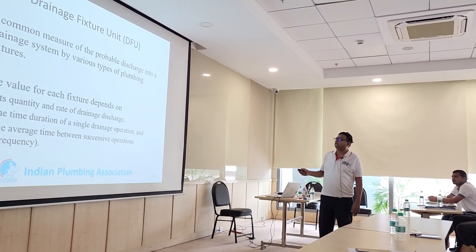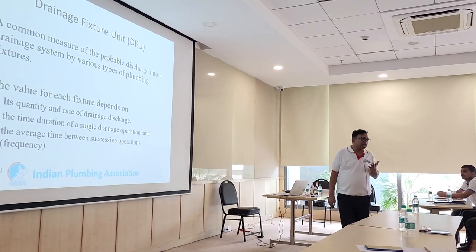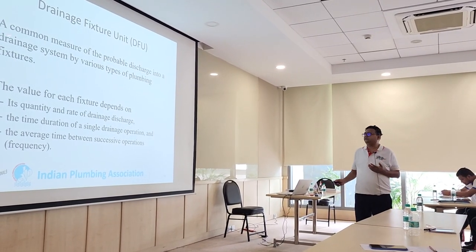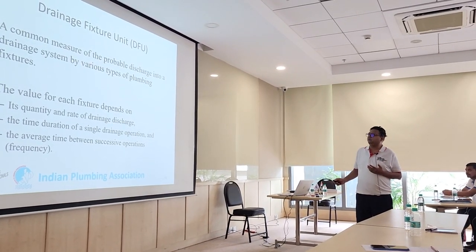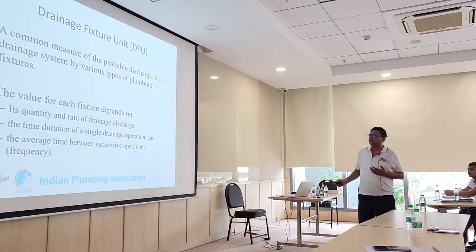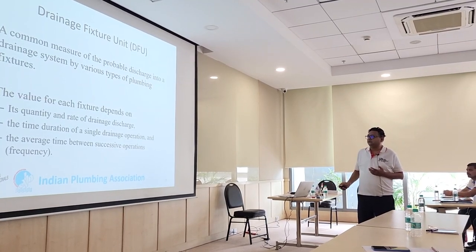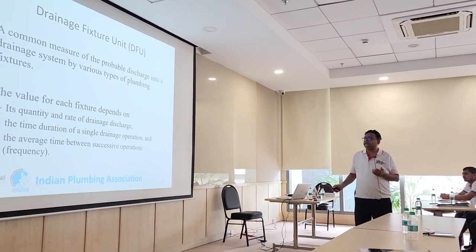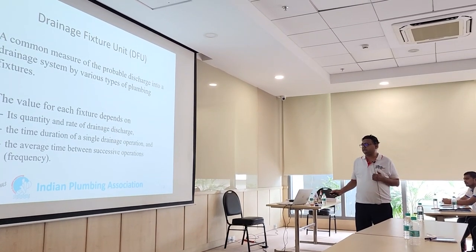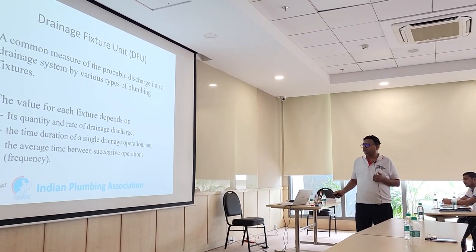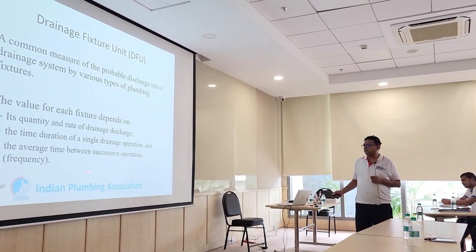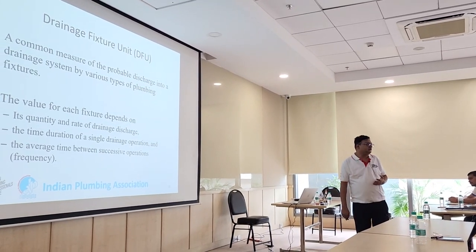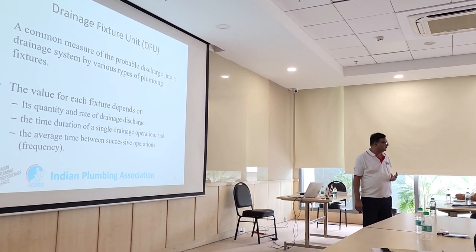Drainage Fixture Unit (DFU) — this was covered in the first lecture also. It is a common measure of the probable discharge into the drainage system. The value of the Drainage Fixture Unit (DFU) depends upon its quantity and rate of drainage discharge, the time duration of a single drainage operation, and the average time between successive operations.